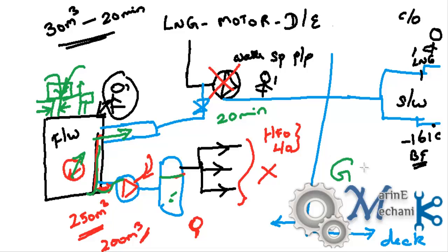We raised a guarantee claim and then pushed a message to the yard stating that the air vent is of less capacity and they have to replace the vent size. The vent size is not sufficient to accommodate the spray pump suction. The yard people came out with a solution. They fixed a new air vent on both fresh water tanks, port and starboard side, and then we tried out the spray pump. The problem was solved.